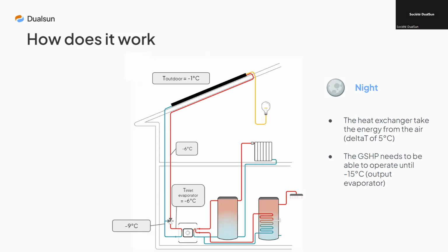The idea is that the more I put pressure on my heat pump during the transformation, if I come in at -5 degrees and have to go out at 30 degrees, my compressor will have to work harder. So I'll need a lot more kilowatts of electricity, which will inevitably reduce my COP. To get a clear idea, we need to look at the SPF and look at the real efficiency of the installation over the year, as we'll see next.